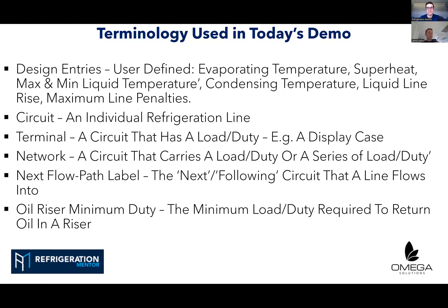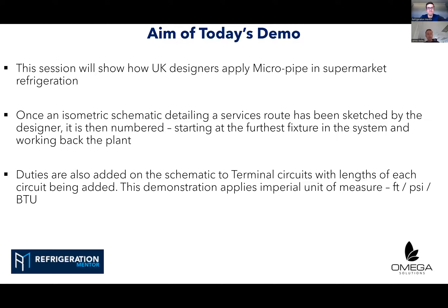We number up from the isometric. If it's circuit one, circuit one may go into number two, three, four, or five — but it's sequential, and the software flags it if you try to label more than two circuit numbers as your next flow label. For suction line oil risers, it allows us to put in minimum duty for oil return — a really cool feature so we don't oversize those risers, which can cause a lot of problems in winter or summer months if the riser is too small, resulting in excessive line losses and penalties.